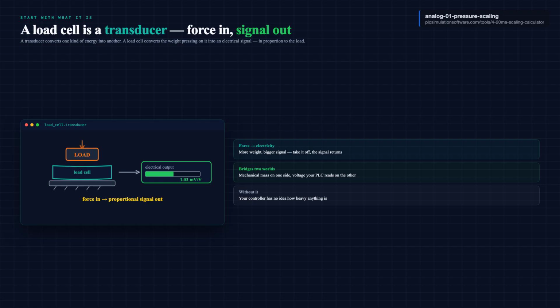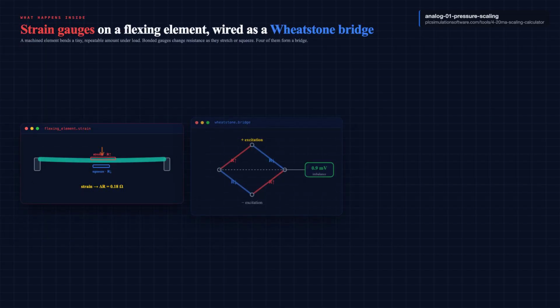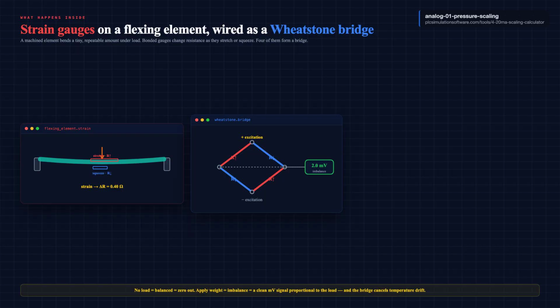Look inside. There is a precision-machined block of metal, the flexing element, sometimes called the spring element. It is built to bend by a tiny, repeatable amount under load. Bonded onto that metal are strain gauges. A strain gauge is a thin foil grid whose electrical resistance changes when it is stretched or squeezed. Stretch it, resistance goes up. Compress it, resistance goes down. The change is minuscule, so we need a way to read it precisely. That is the Wheatstone bridge.